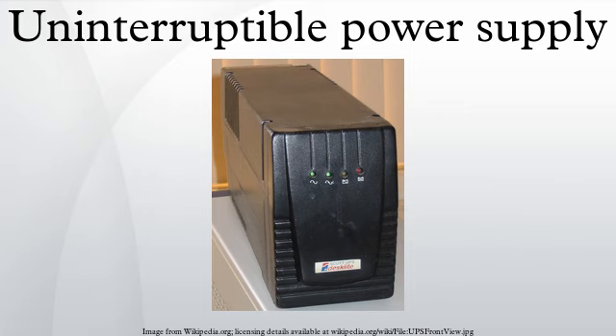Form factors. UPS systems come in several different forms and sizes. However, the two most common forms are tower and rack mount. Tower model. Tower models stand upright on the ground or on a desk or shelf, and are typically used in network workstations or desktop computer applications. Rack mount model. Rack mount models can be mounted in standard 19 inch rack enclosures and can require anywhere from 1U to 12U. They are typically used in server and networking applications.